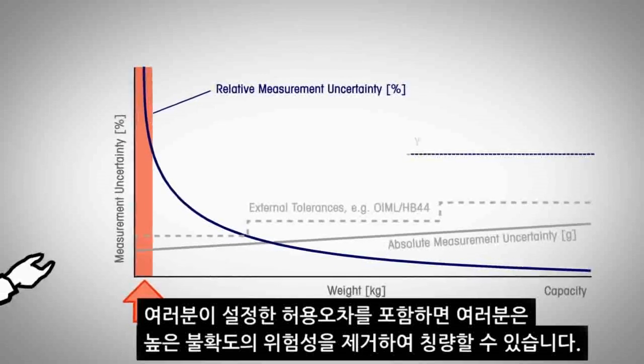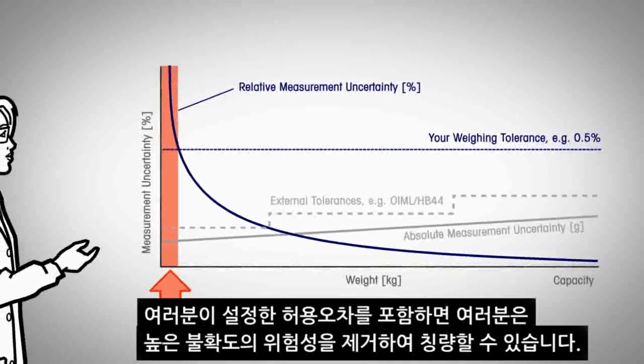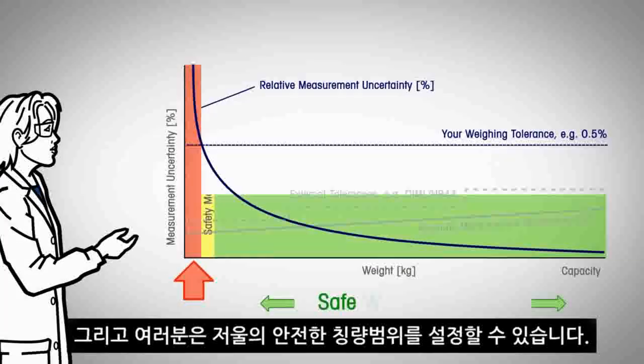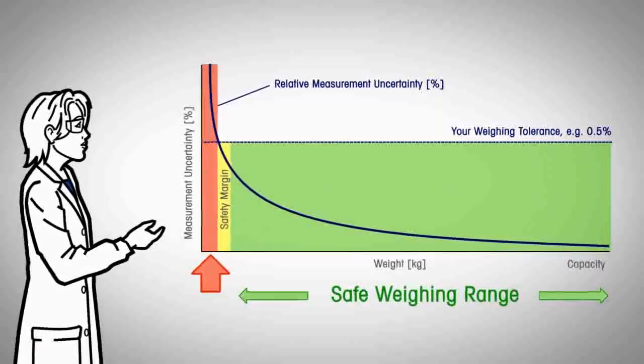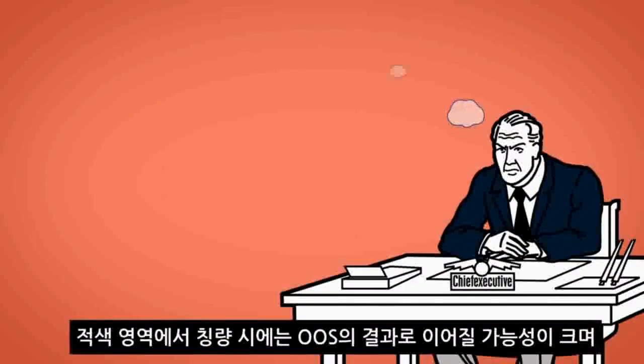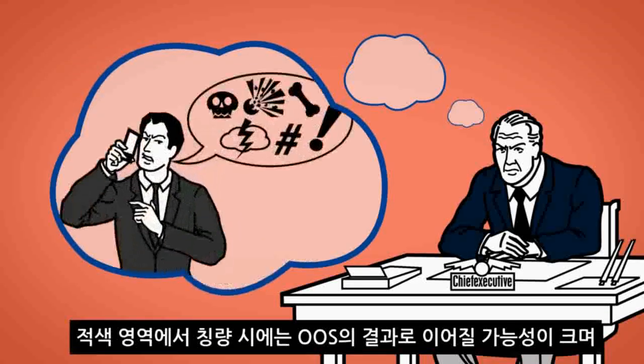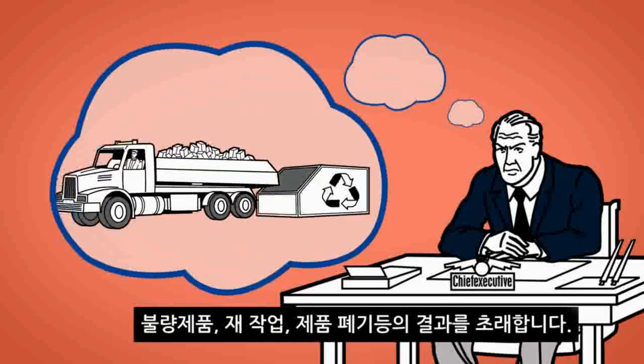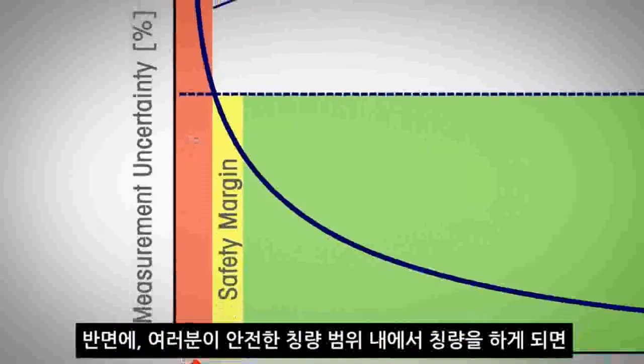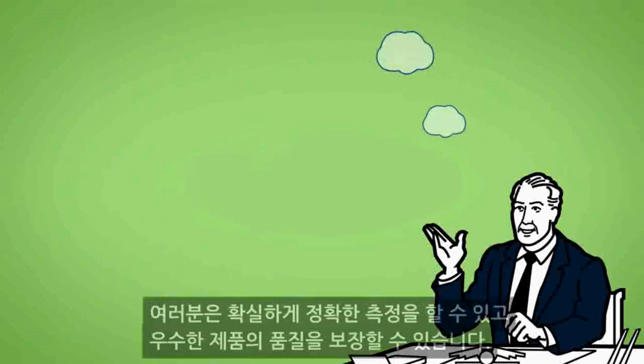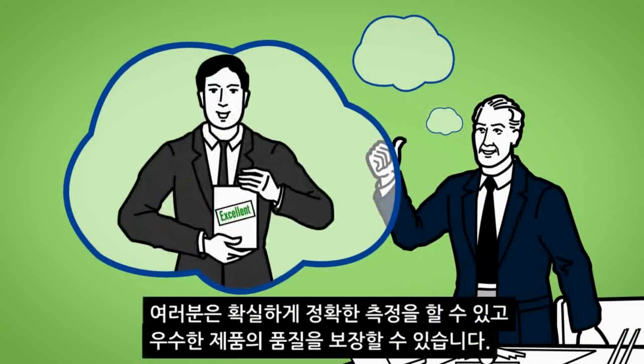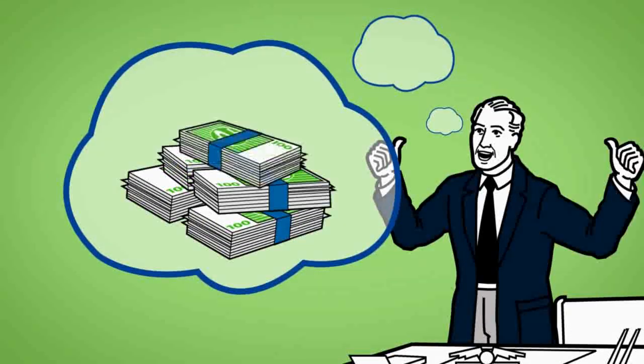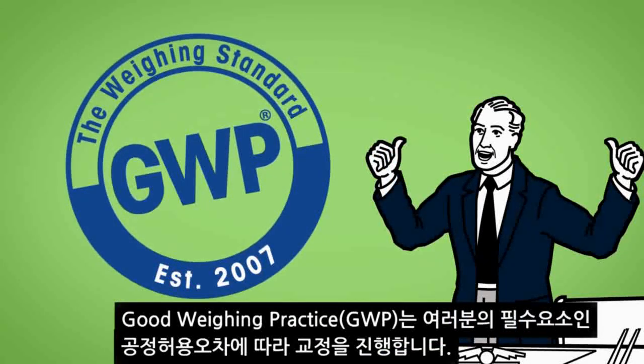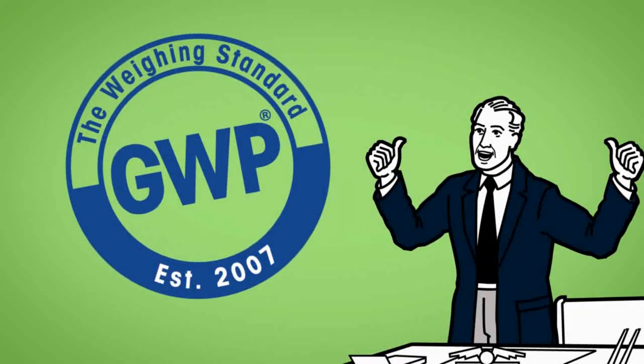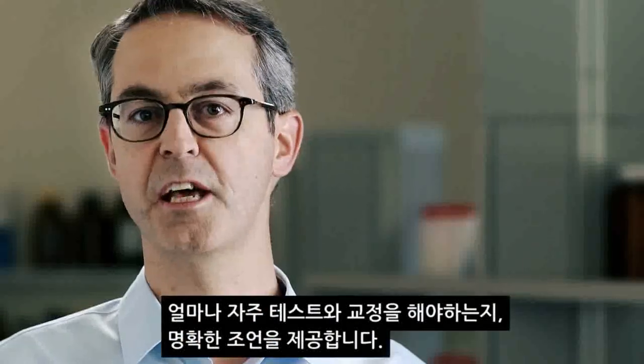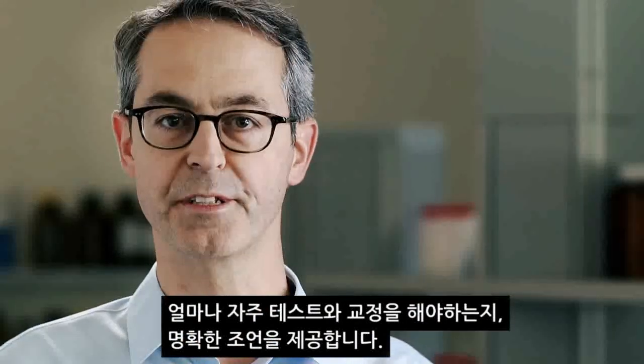Including your tolerances eliminates the risk of weighing with too high uncertainty and establishes the safe weighing range of your equipment. Weighing inside the red area leads to potential out-of-specification results, bad product quality, rework and waste. On the other hand, when you weigh within the safe weighing range, you ensure accurate measurements and guarantee excellent product quality. Calibration according to your process tolerances is an essential part of good weighing practice. GWP also provides you with clear advice how often you should calibrate and test your weighing equipment.